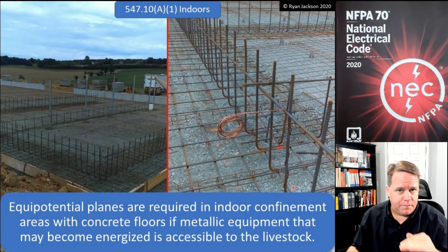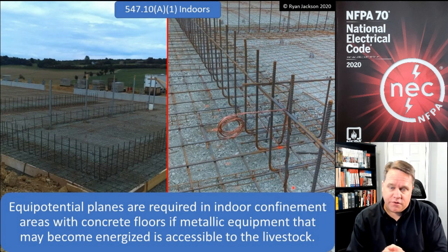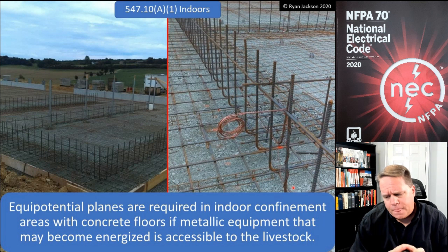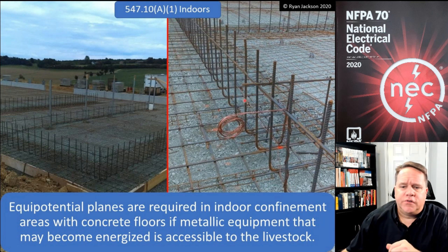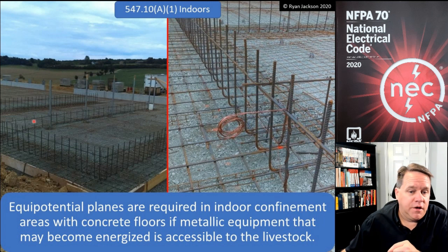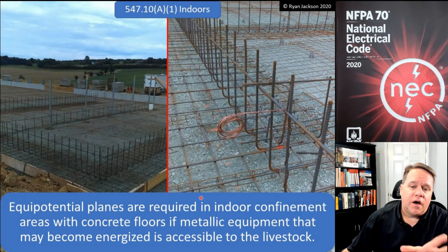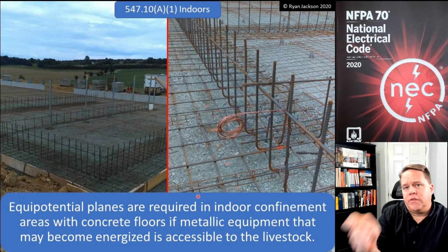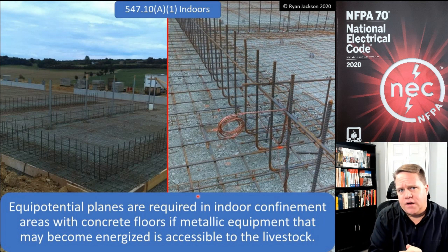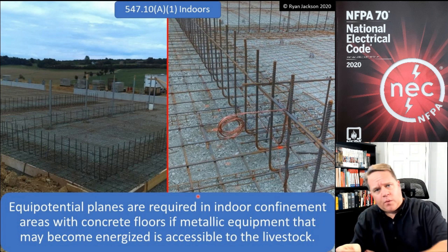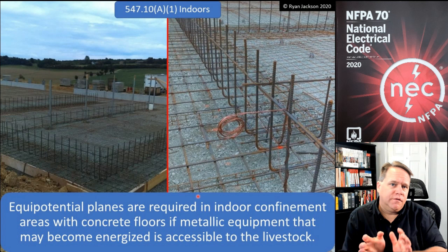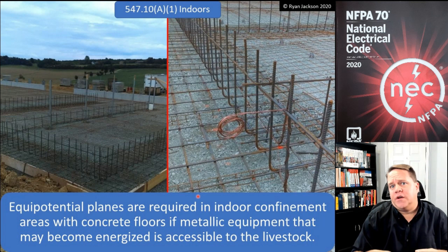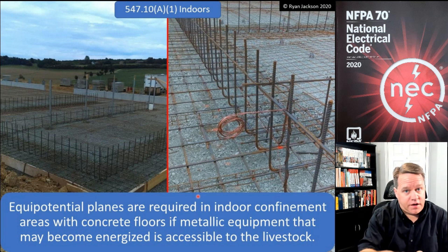We need to make sure cows aren't experiencing differences of potential when they walk around inside a barn, or especially when going from outside to inside. Article 547 requires rebar throughout the concrete slab in the barn, with all the rebar tied together using typical tie wires, then bonded to the service equipment and panelboards. This ensures everywhere the cow walks is at the same voltage. In some dairy farms, they'll actually create an equal potential ramp where the cows walk into the barn.